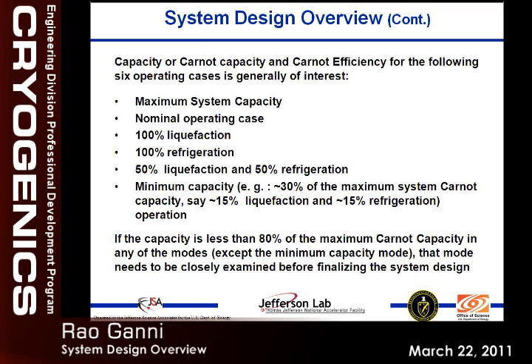Another thing is, like we said, we really don't know exactly our loads. We'd be kidding if we say we know exactly what our load is. It changes every minute. It depends on outside temperature. It depends on the vacuum in the cryomodules, or the transfer line, or the cans. Everything has an impact on the energy of the beam they want. They're all varying constantly. Nothing is given. Although we say, yeah, we want the system designed for one thing, that's a myth. That's one design point to simplify it so that we can measure or something we feel comfortable about in acquiring a plant. But that's how we sold a lot of plants, we bought a lot of plants.